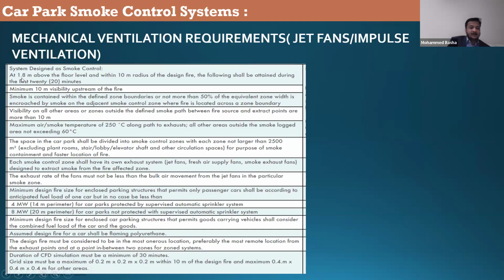So here, if you see, at 1.8 meters above the floor level and within a 10 meter radius of the design fire, the following shall be attained during the first 20 minutes. You need to have 10 meter visibility. Smoke is contained within defined zone boundaries, or not more than 50% of the equivalent zone. I mean, within 50% of the car park, the smoke should be contained. Visibility should be 10 meters in all areas. Maximum temperature 250 degrees Celsius along the path to the exhaust, and all other areas outside the smoke-logged area not exceeding 60 degrees.